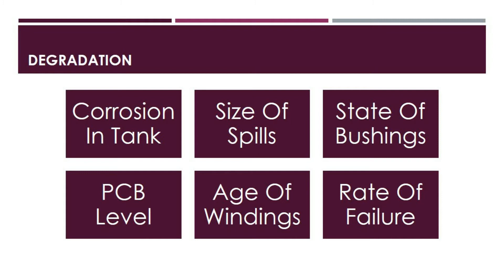Visual examinations provide a wealth of information about a transformer's condition. They can reveal leaks, fractured bushings, and rusting in tanks, among other things. When considering the environmental safety issue, the level of PCB or polychlorinated biphenyl insulation oil should be investigated. The main effects of a distribution transformer failure are reliability issues, which are mostly minor. This is why most utilities run their home distribution transformers to failure. Larger distribution transformers supplying commercial or industrial clients, however, may have a significant impact on reliability, and therefore transformers may be replaced as they near their end of life.